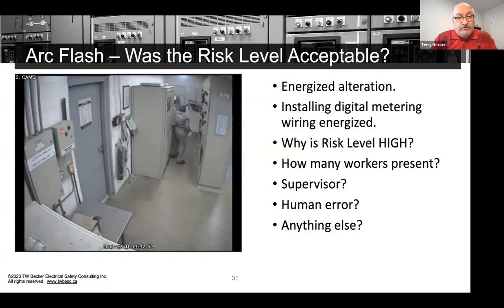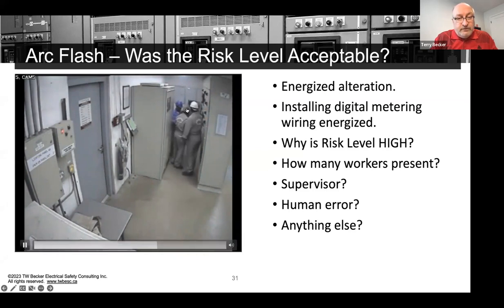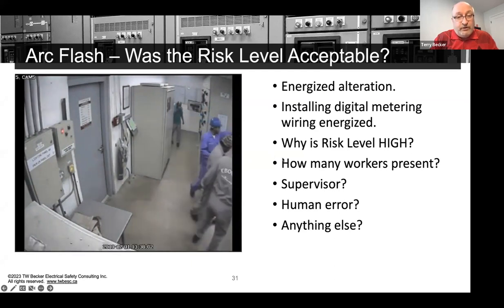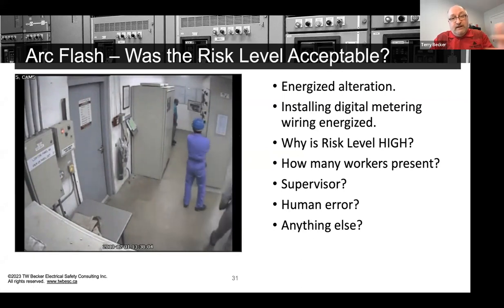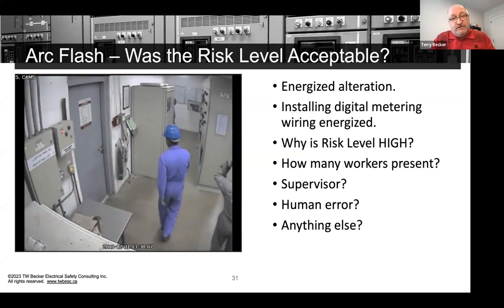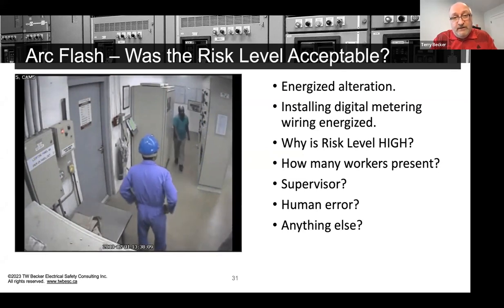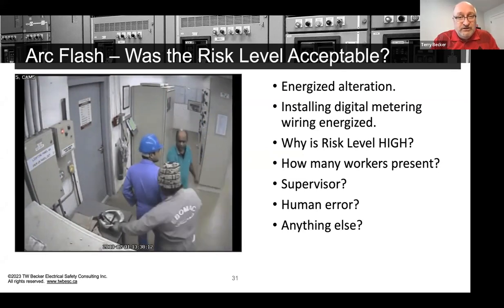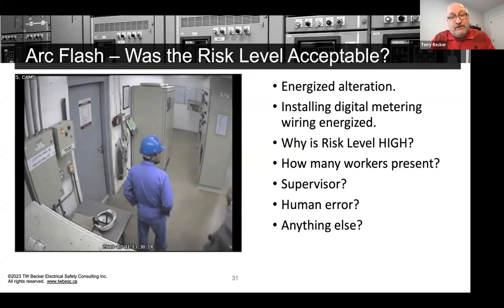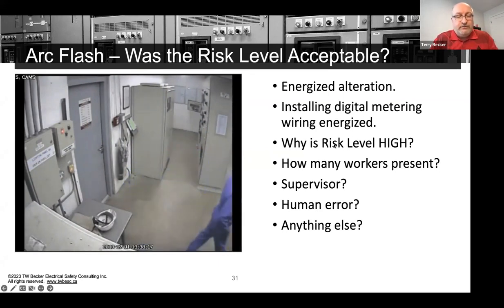So the other thing too is watch the gentleman in the golf shirt, sort of the green golf shirt. He's still looking inside the MCC, and there's a secondary abnormal arcing fault, right? So the thing is, any incident, get away from that scene because a hazard could still be there. In this case, it was. And then what do they do? They leave the incident scene unmanaged and walk away from it, and someone could still come in. So there was no identification of arc flash or shock. There were no boundaries. There was no electrical work zone. There was no PPE worn by the primary worker. And he was doing energized alteration, which we need to eliminate as a priority.